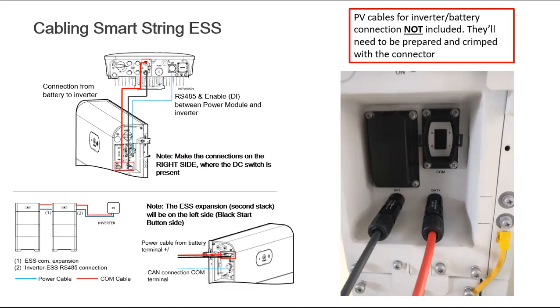So you use those connectors and crimp them properly, and then connect the power cables directly from the inverter to the power control module. Make sure that you connect the inverter power cables onto the right side of the battery. I have seen in some installations that customers are connecting the power cables onto the left side of the power control module. The left side of the Luna is used if you are cascading the batteries, or if you are using the 30 kilowatt hour system. In that case, you use the left side connectors to connect from the battery. And if you are connecting the battery with the inverters, always make sure you use the right side connectors to connect to the inverter.